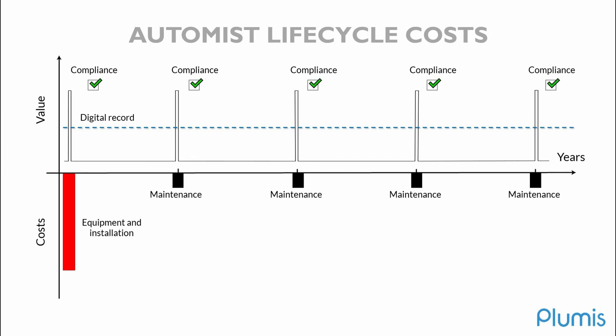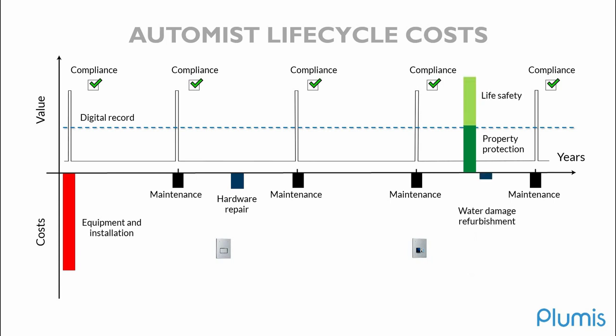The difference comes in if a boisterous tenant is intent on breaking one of the heads, then you do have a hardware repair cost. And similarly, if you have a fire, the system will activate, you get that suppression taking place, you get the property and the life safety benefits that you would with a sprinkler. But again, you're limiting the amount of water damage that takes place and the relocation costs because you don't have that 60 liters of water as a consequence of action.